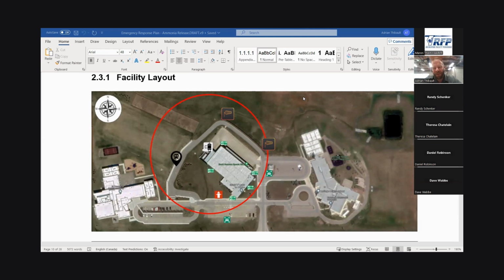Yeah, with the low charge, we're talking about 440 pounds, which is a low charge. We're a single pad rink. So we made a 300 foot isolation zone from the plant room based on 1,000 pounds. Or no, sorry, 900 pounds.